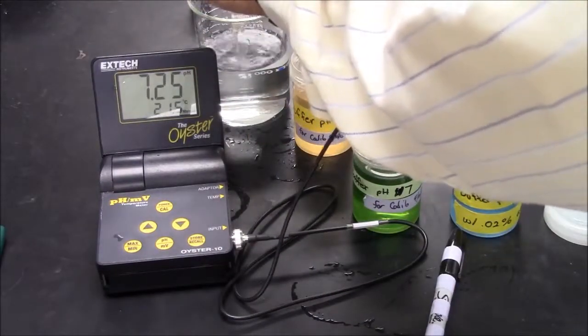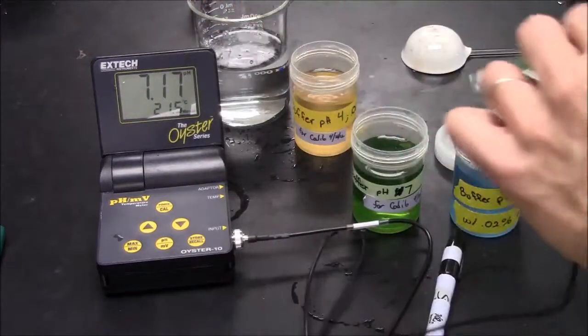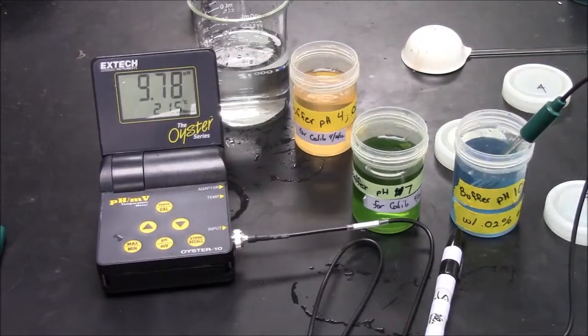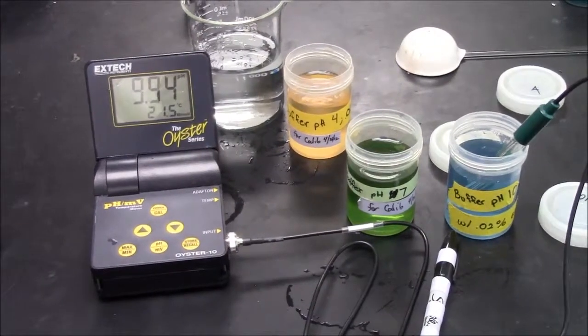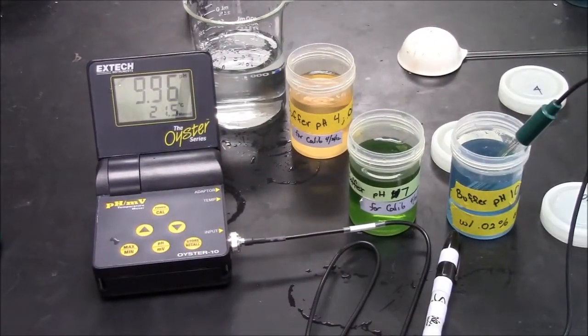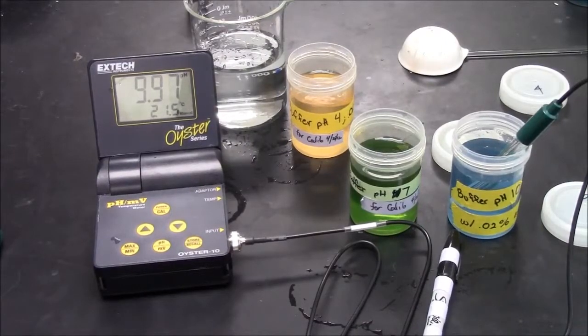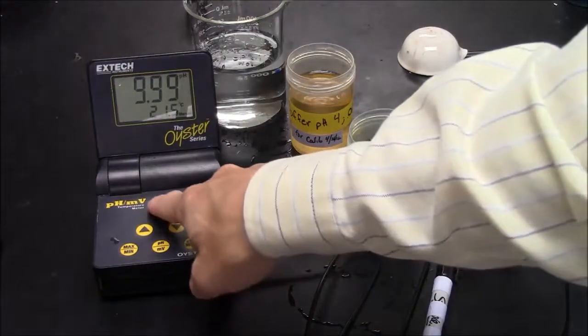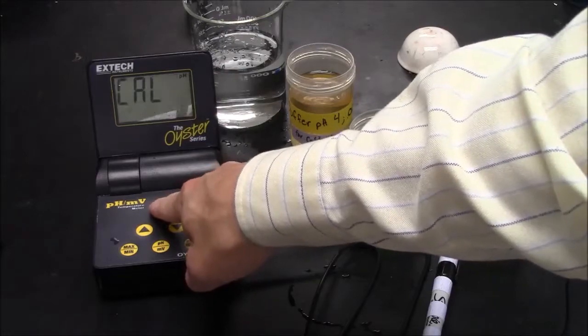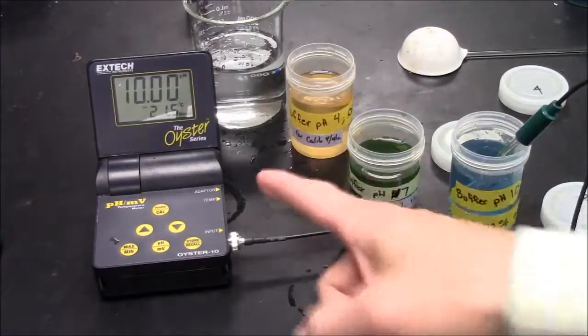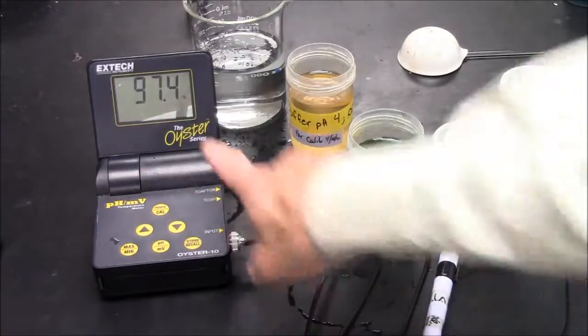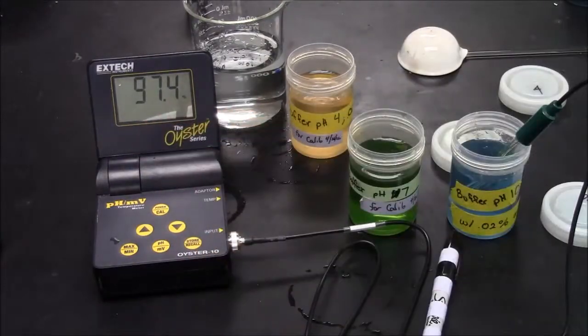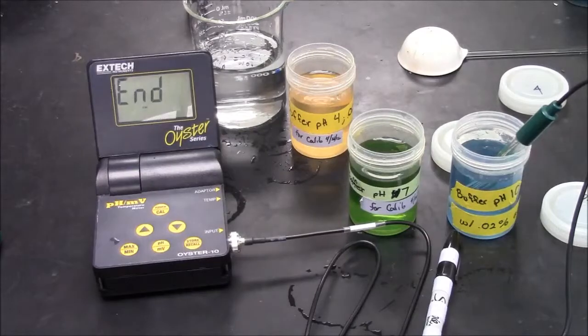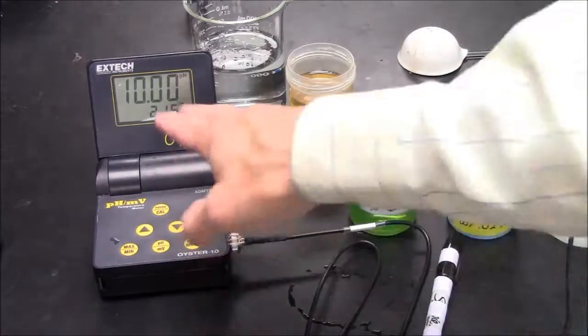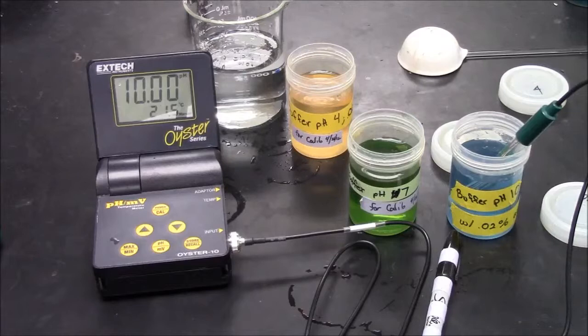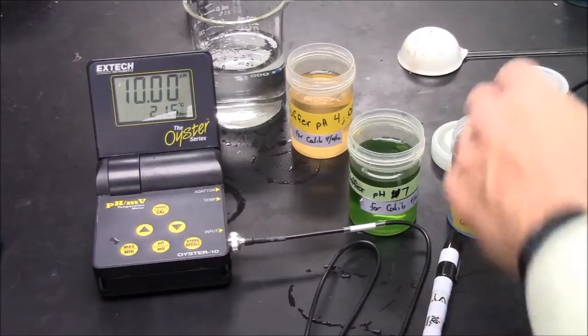Rinse off the electrode with distilled water. Immerse the electrode in the pH 10 buffer. Again, give it a minute or so to equilibrate. I will press and hold cal until it says cal. It will now say this is 10.00. It gives me a percentage. The closer that is to 100, the happier I am. If the percentage read something like 82 or 78, it would be time to replace this electrode.